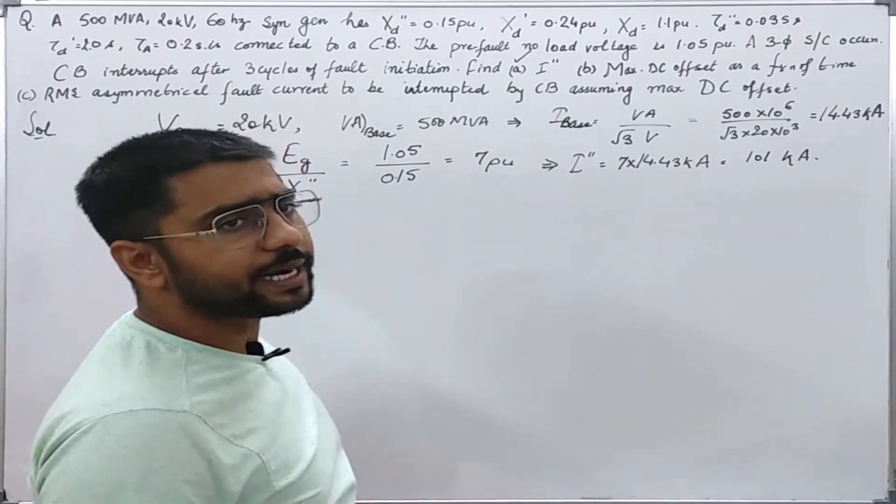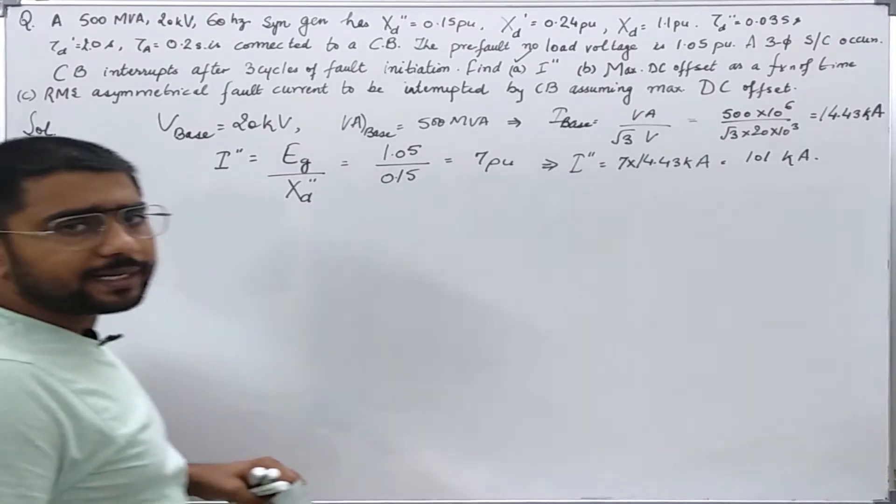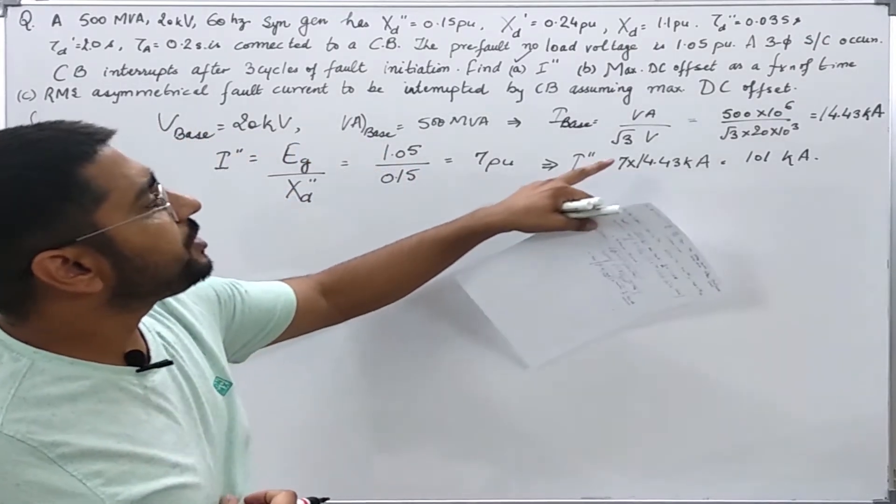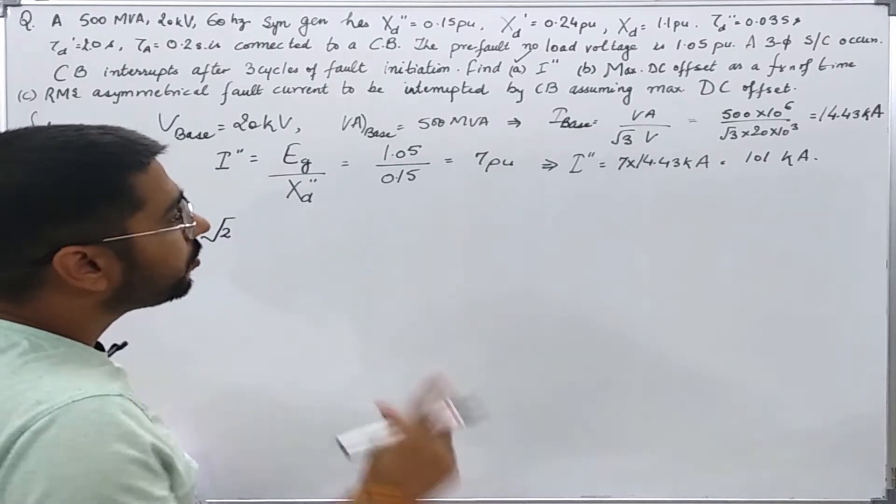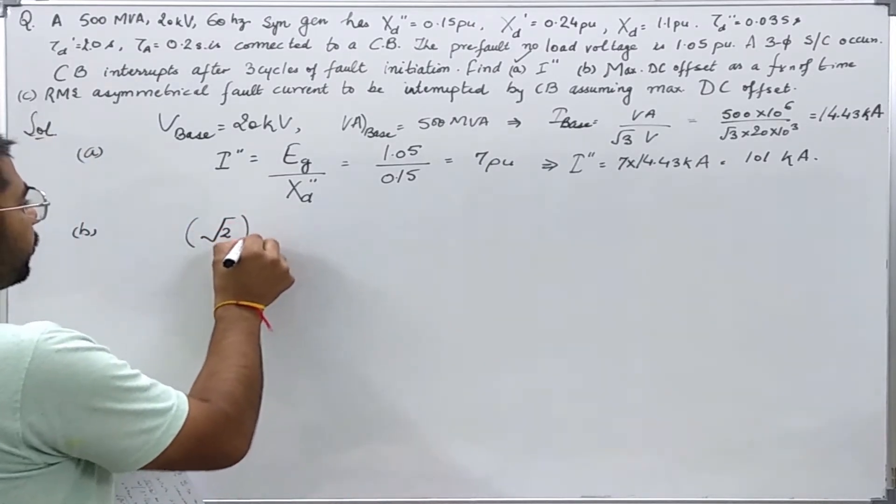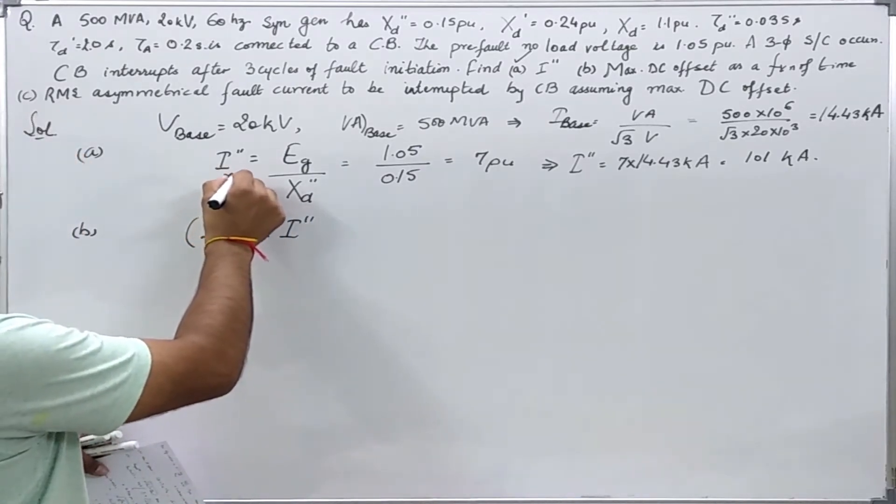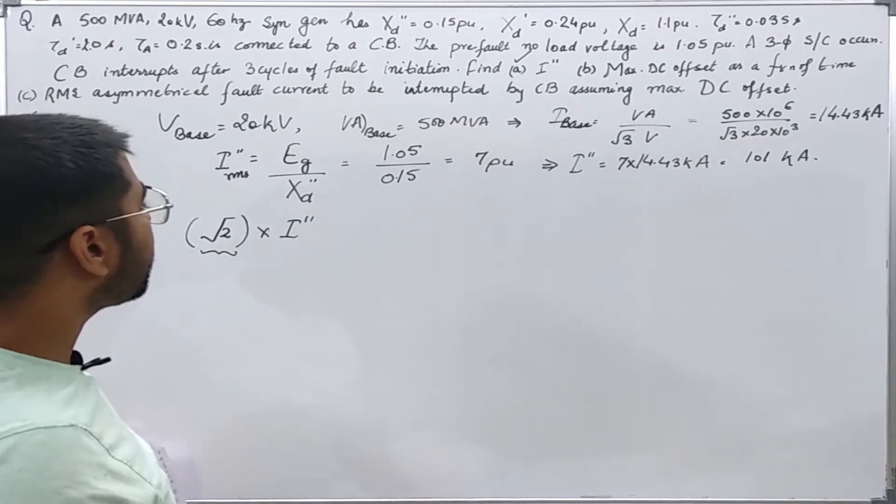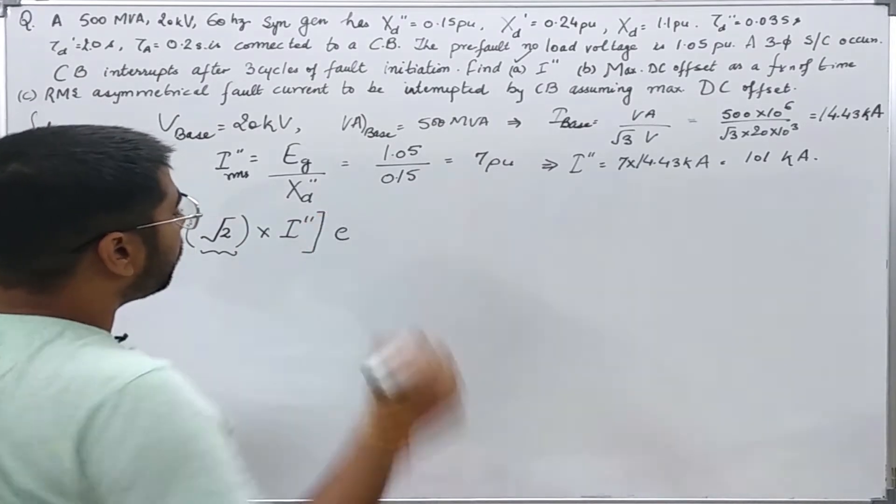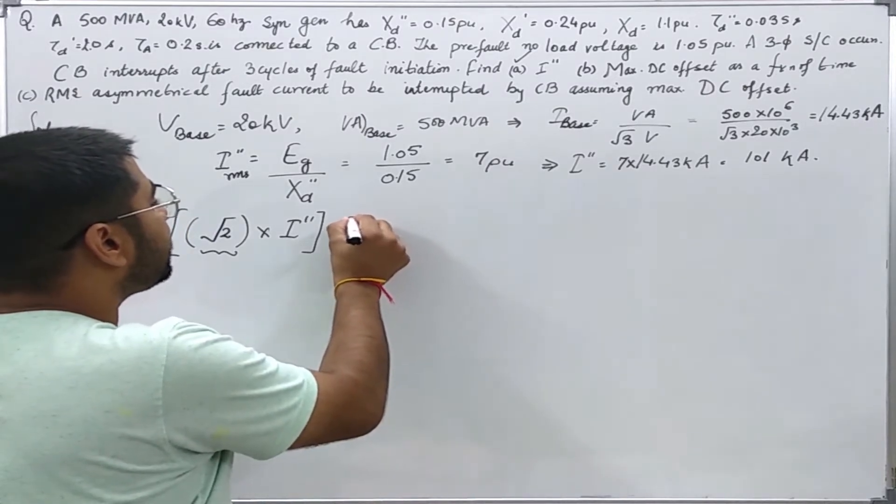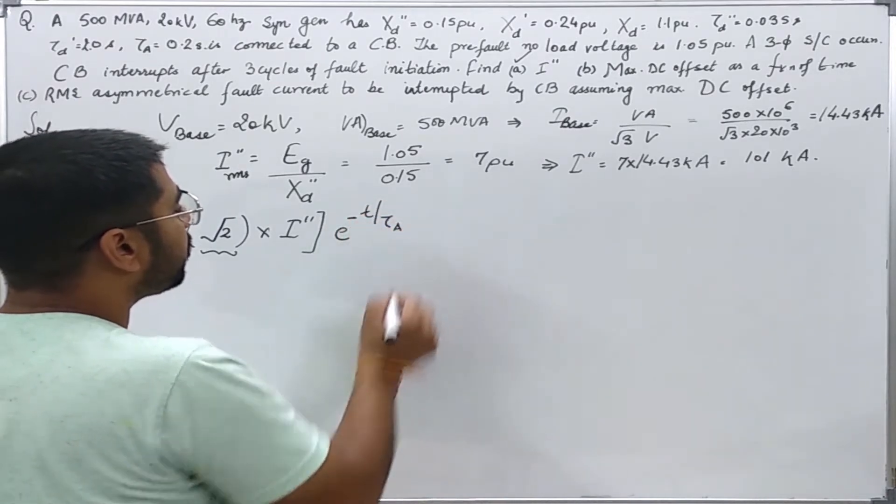Now we will move on to the second part. In our lectures we have seen that the maximum DC offset can have a value which is equal to the maximum value of the symmetrical fault current. That is it can have value root 2 times the sub-transient fault current value. This is an RMS, that's why I have to put root 2 here. Now this DC offset will dissipate or die down with exponential form and since it is flowing in the armature winding, its time constant will be the same as the armature winding time constant.